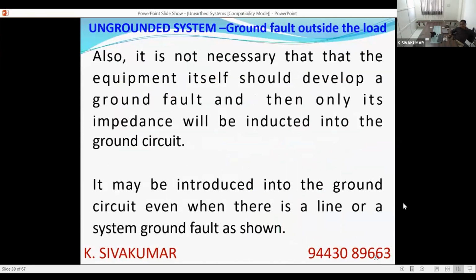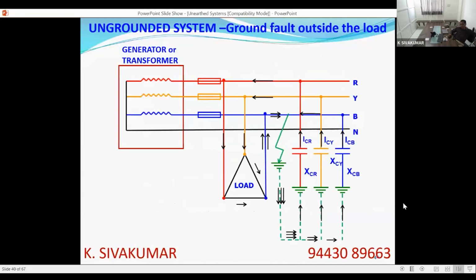So, moreover, it need not be that the fault happens inside the load or the source. Even if there is any system fault in the network, the impedance will be introduced into the ground circuit like this. If you can see this circuit, in this circuit also the fault is not in the equipment. The fault is outside the equipment, in the network cable or the network line. You can see here also the load impedance is introduced in the ground circuit.